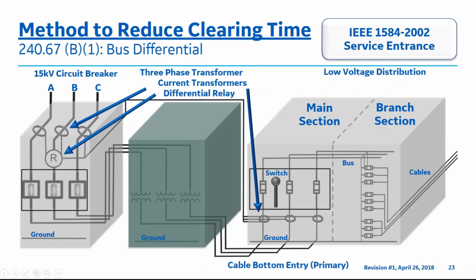During the various forms of arcing faults documented on the previous slide, the transformer protective relay with the 87T function, along with current transformers, along with retrofitted CTs, are included as examples in the main section. In this slide of the low voltage distribution section, a protective relay is measuring and clearing these arcing current events between the medium voltage switchgear and the low voltage CTs, located just ahead of the primary fuse switch in the main section in the low voltage distribution section.